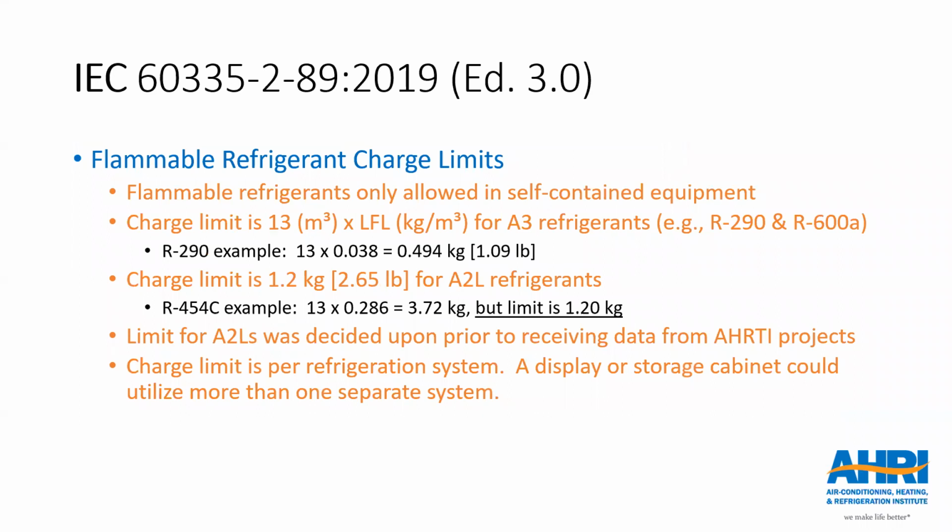Starting with the new IEC edition 3 of 2-89, the single most significant change in this edition was the increase in the charge limits for flammable refrigerants used in commercial refrigeration equipment. So importantly, flammable refrigerants are only allowed in self-contained equipment.